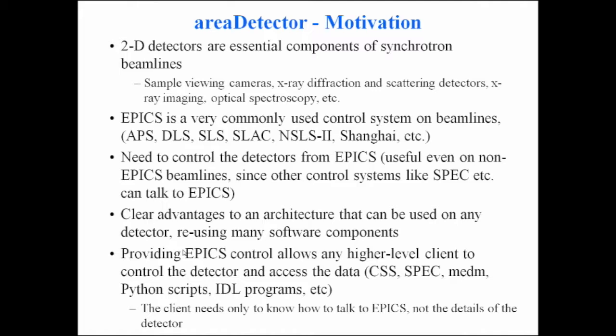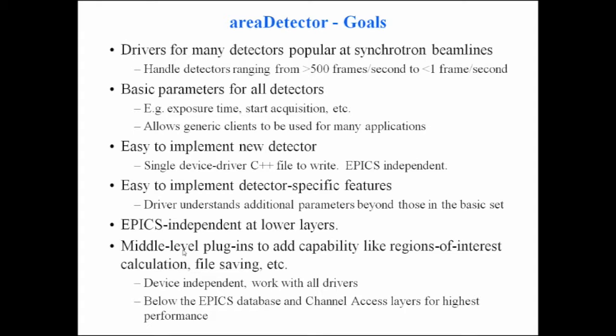There are clear advantages to having a framework or architecture that can be used on any detector, letting you reuse lots of software components. By putting EPICS control on a detector, you let any high-level client — Control System Studio, SPEC, MEDM, Python, IDL — control the detector and access the data. The client only needs to know how to talk to EPICS, not the details of a particular detector.